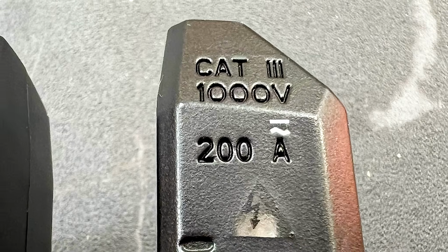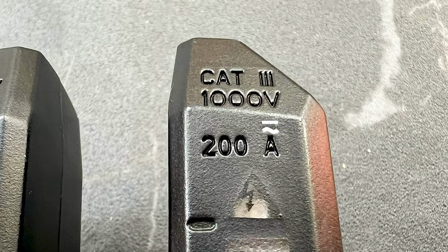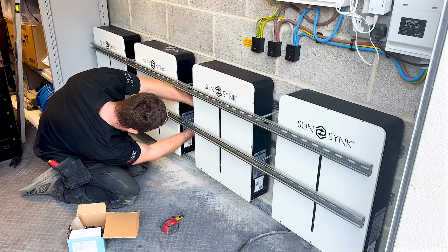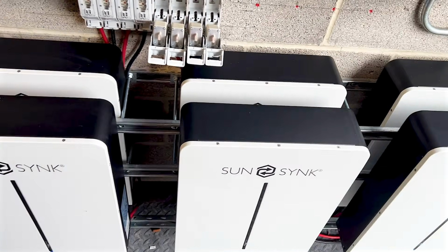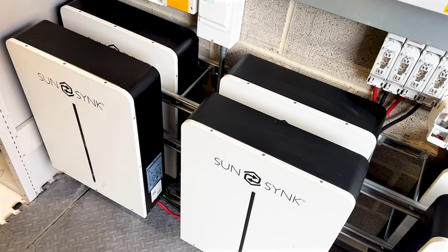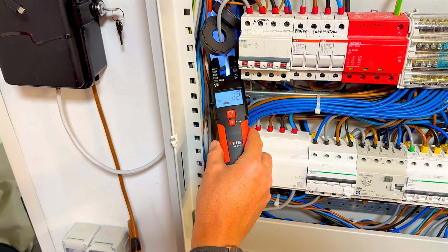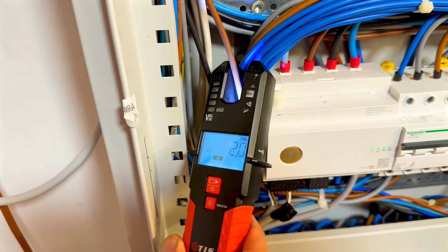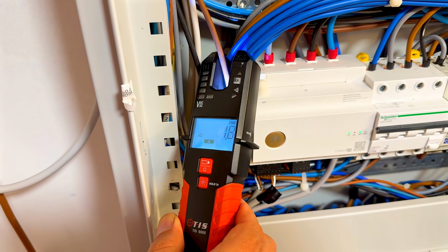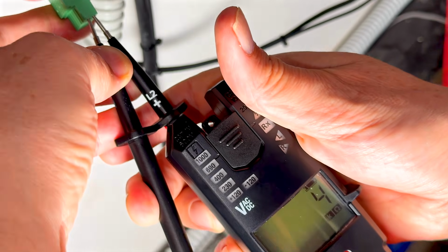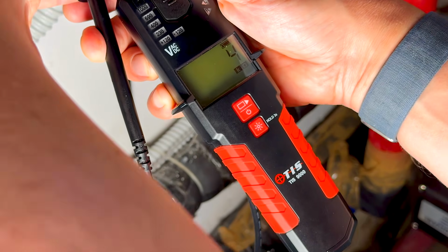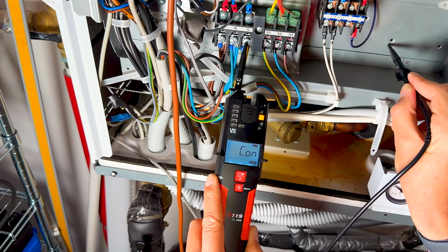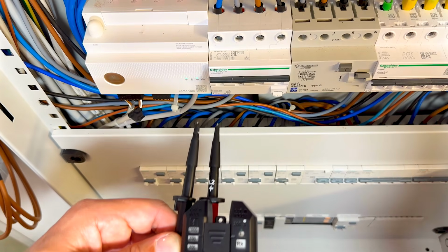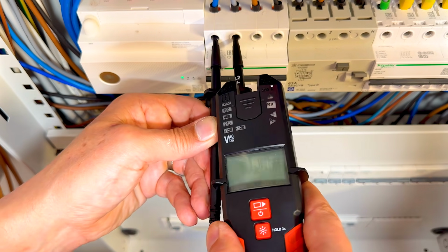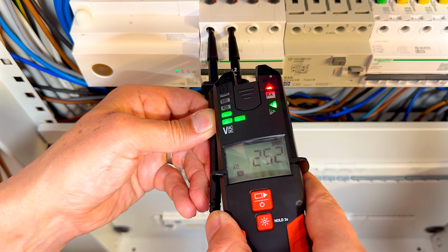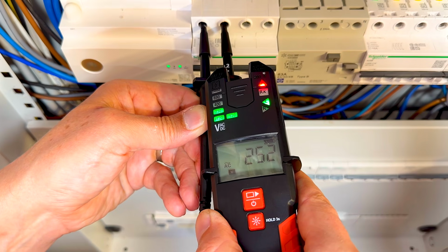On the current side, the open jaw clamp will measure up to 200 amps DC. That's particularly useful when you're working on parallel strings or inside battery systems where multiple batteries are connected together. And on the AC side, again 200 amps, it gives you a quick and easy way to check current draw on a circuit without breaking into it. Alongside voltage and current, the tester also covers your core electrical measurements. You can measure resistance, check continuity, and test frequency. It will also handle phase rotation, which is particularly useful when you're working on three-phase systems and need to confirm everything's running in the correct direction.